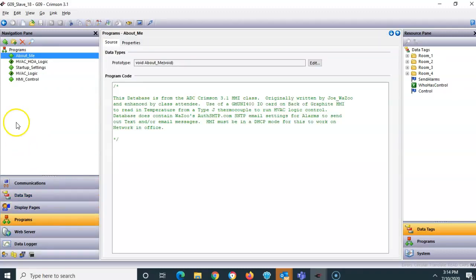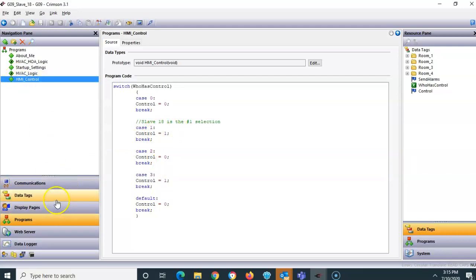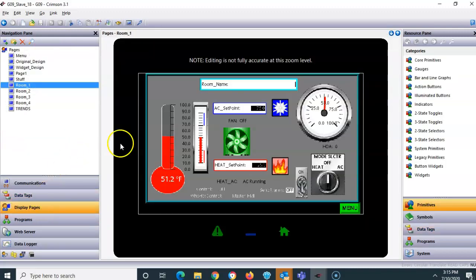For the logic, I wrote a program called 'HMI Control' using a switch-case method. You feed the switch-case function a variable, and it's basically a giant if-then loop. If the variable equals one, I set a tag called 'control' to one, meaning this HMI has control. The other cases handle slave 18 and so on. The control bit is a flag tag.